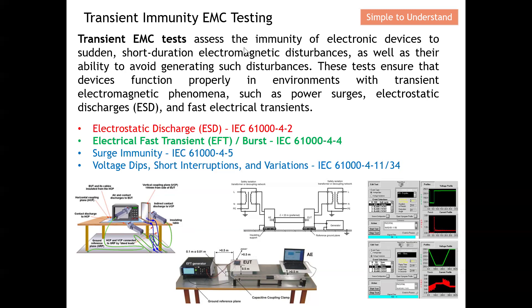Transient EMC testing mainly assesses the immunity of your electronics device to sudden, short-duration — can be micro or nanosecond — electromagnetic disturbances, as well as their ability to avoid generating such disturbances. Once you build your DUT, you test them under a quick short duration and see whether your DUT can still function. You also need to ensure your DUT will avoid generating such disturbances to neighboring devices. This test ensures the device functions properly in an environment with transient electromagnetic phenomena, such as power surge, electrostatic discharge, and fast electrical transients.